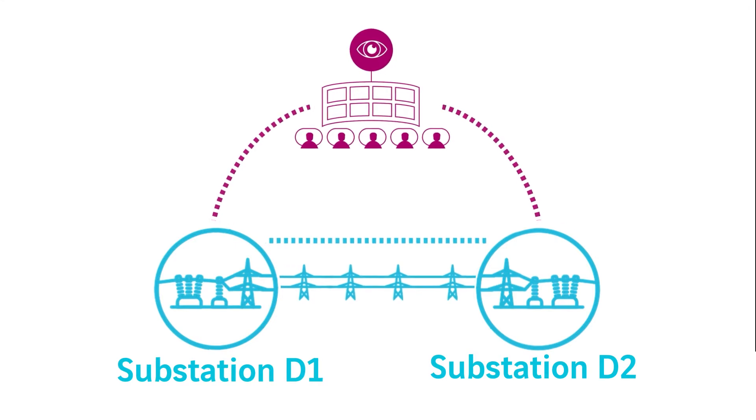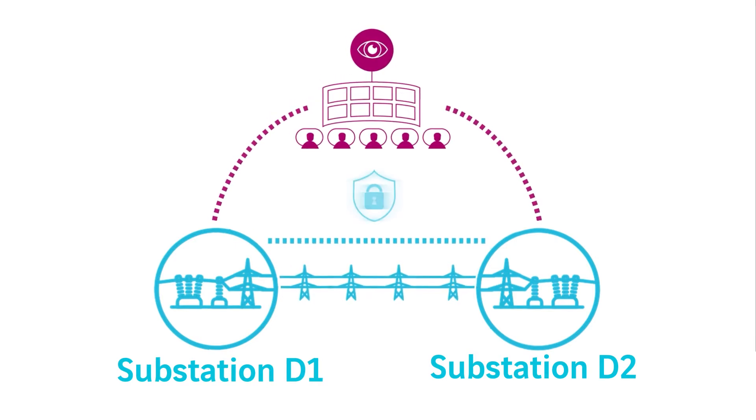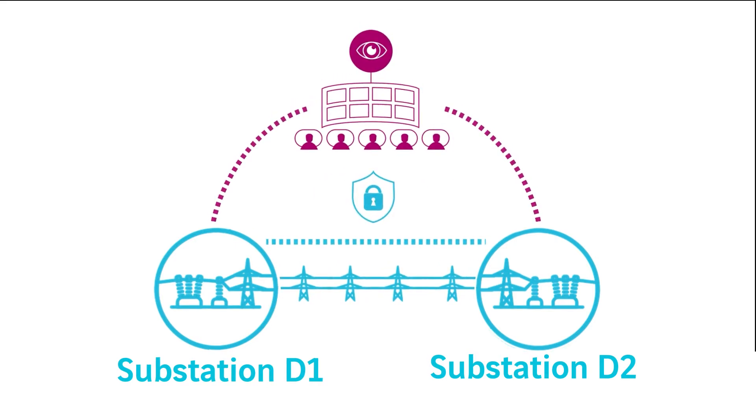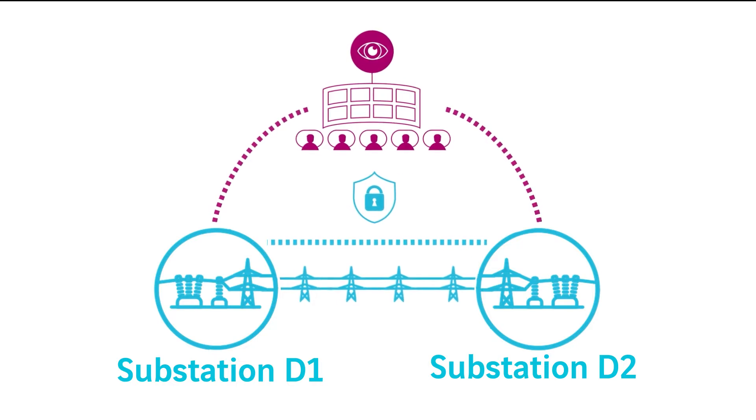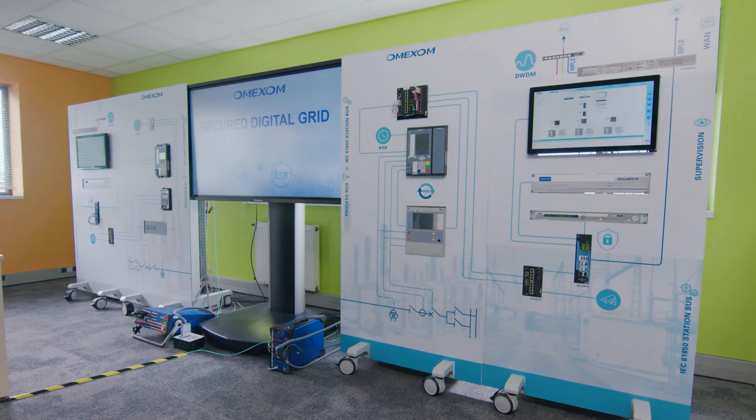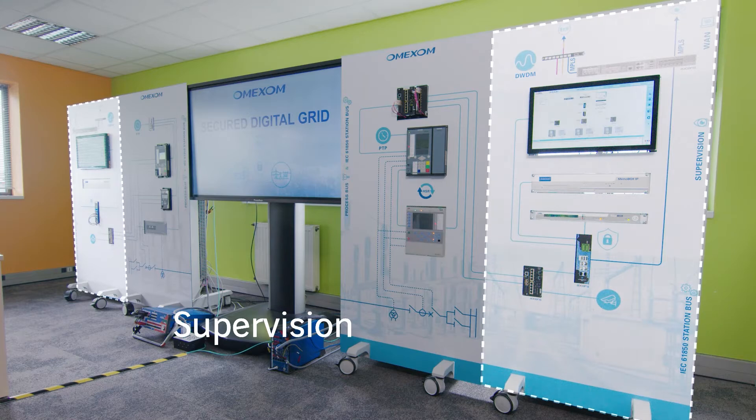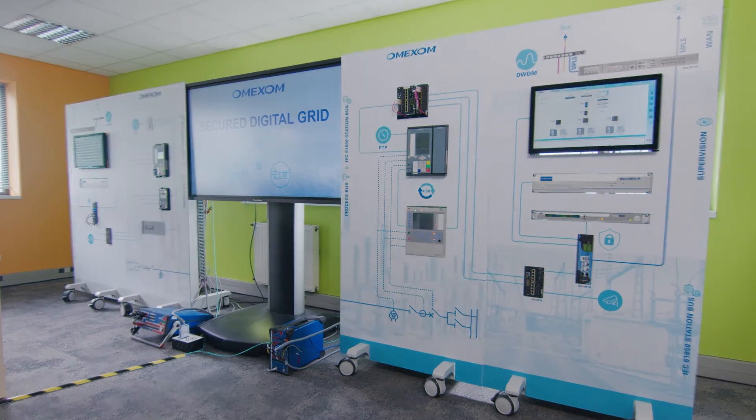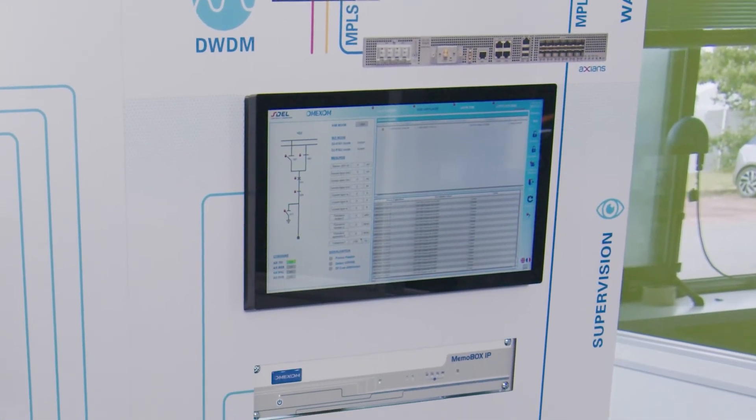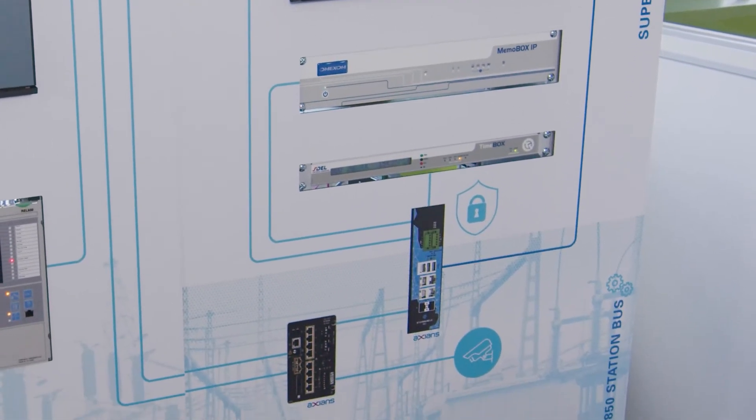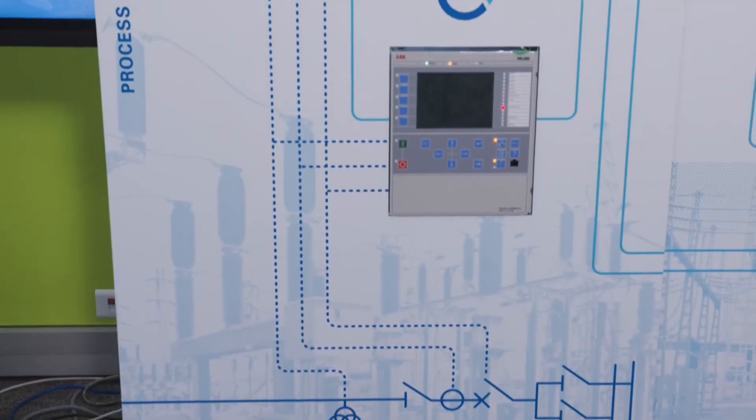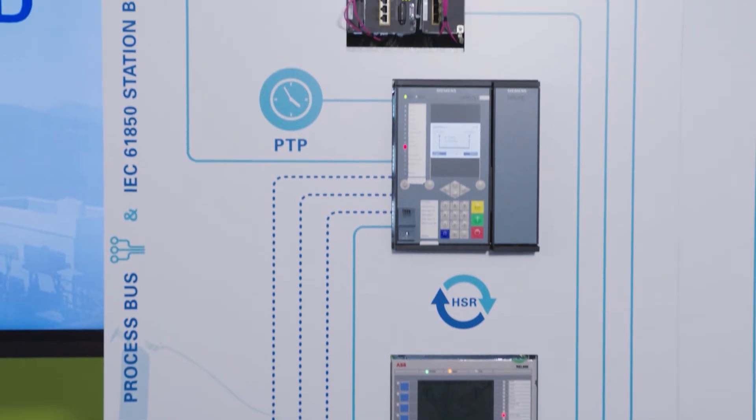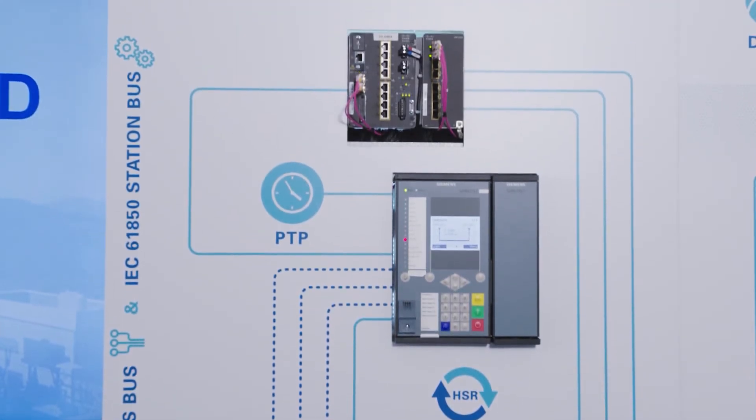This network serves as an information exchange channel for the protection of the line. The network is controlled thanks to the exchanges between the control center and each substation. Each substation consists of a supervision system and protection devices. The supervision system integrates equipment to control and monitor the substation's structures. The protection devices ensure the electrical safety of the structures through numerical protective relays from different manufacturers.